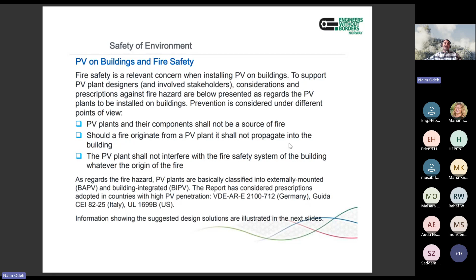Fire resistance of PV modules. Now I'll show you some examples of tests of fire and the design and installation of the system. For the fire, we have 3 criteria and 3 types or classes. There is class A, class B, and class C. The highest one is class A. It is not about fire resistance, but about the time taken, you can say, to catch fire in case of external fire or internal fire. The highest one is A, the average one is B, and I think C is the one commonly used.